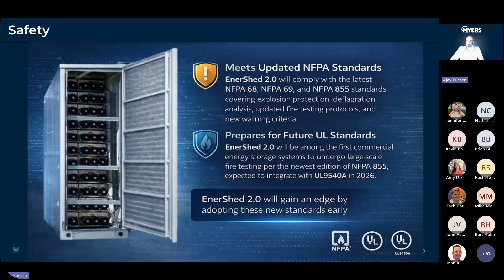What that standard did is actually create the requirement for a new large-scale fire test, one that up until now has not been included in UL 9540 or UL 9540A, but NFPA 855 is mandating that. We are actually in the process of doing that testing with Intertek. And so we're excited to be ahead of the curve when it comes to these safety standards, and it will make your projects with EnerShed 2.0 much easier to permit through an AHJ than, say, somebody else's storage system.